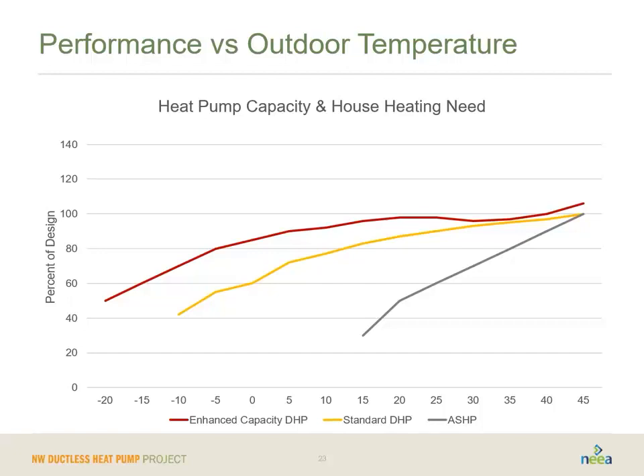There are other ways to look at this. This is heat pump capacity versus the house heating need, shown in a different way. We're going to look at a standard air source heat pump. If you're not colorblind, it's the gray line. If you are, it's the line the most to the right. And we're going to compare that to an enhanced capacity or cold climate heat pump, which is the dark red line, or if you're colorblind, the most left line. Here, again, the bottom is outdoor temperature, and the side on the left is the percent of the design load that you need to meet.